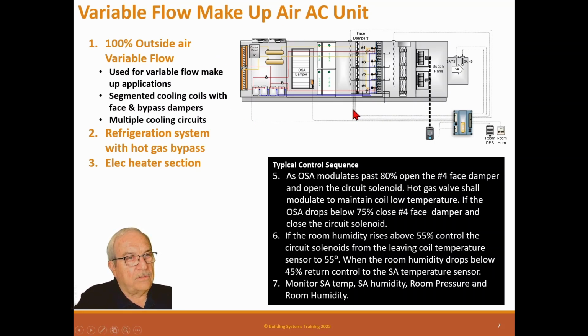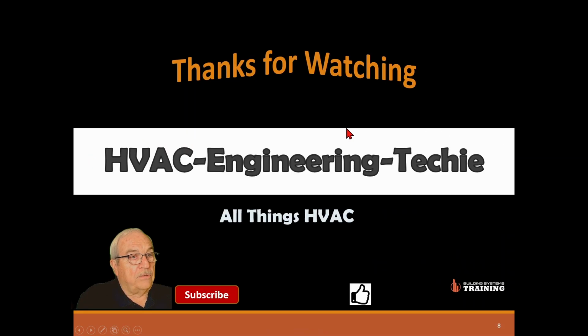So these systems work. They're expensive because they have a whole lot of systems in them. They have 4 separate refrigerator circuits, 4 compressors, 4 VFDs on the fans, and they can provide this to base. Like I said, the one I used was on a marijuana grow room because they needed a whole bunch of outside air at different times of the process. I don't know what that is, but I did help them with this unit. So that basically shows you the variable flow makeup AC unit.